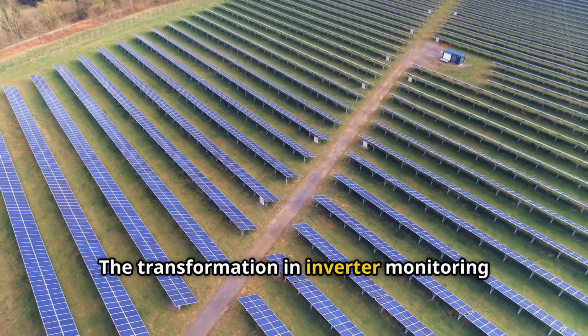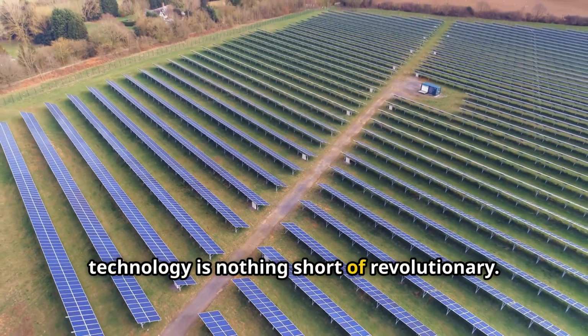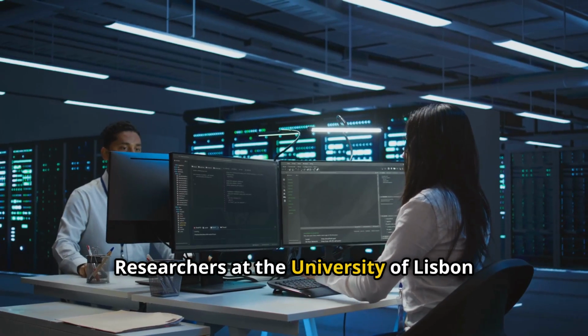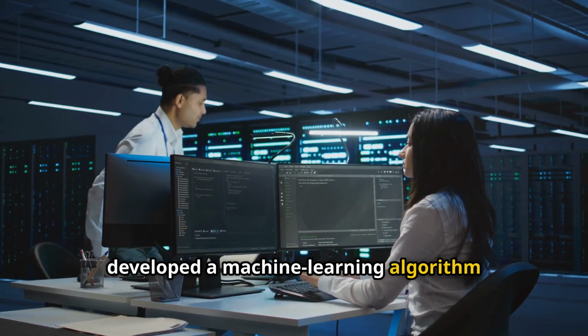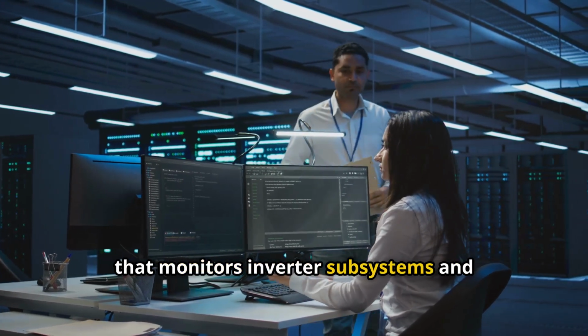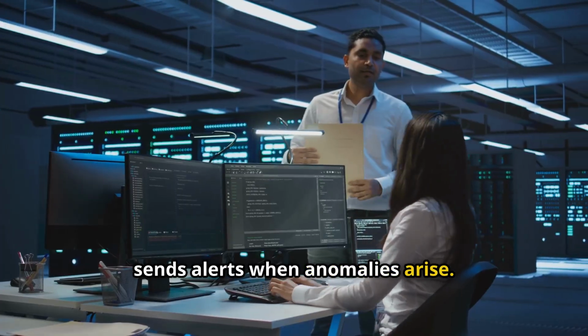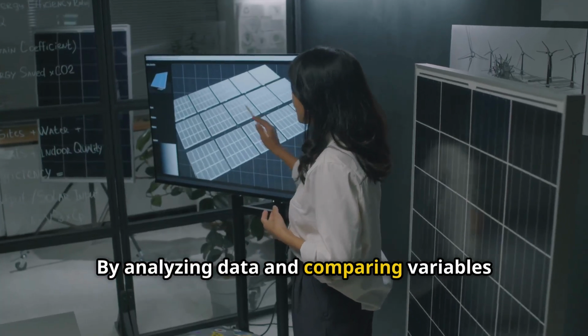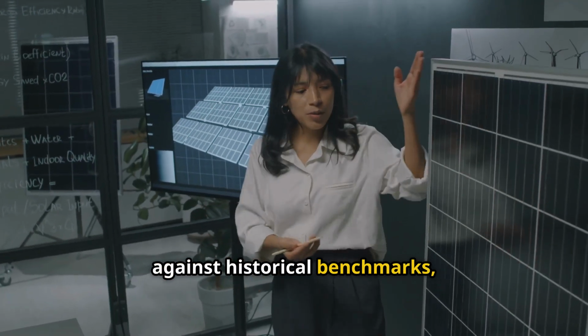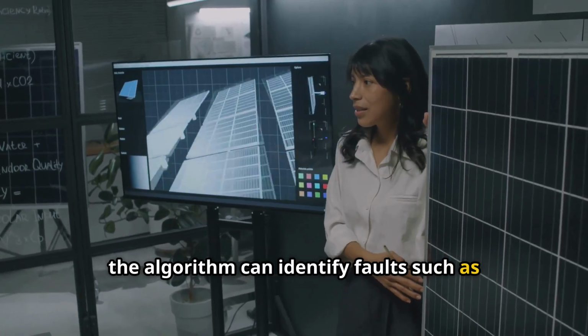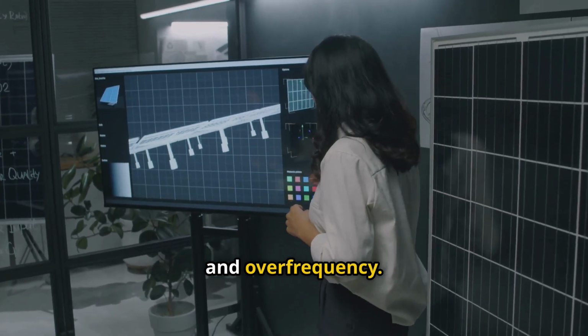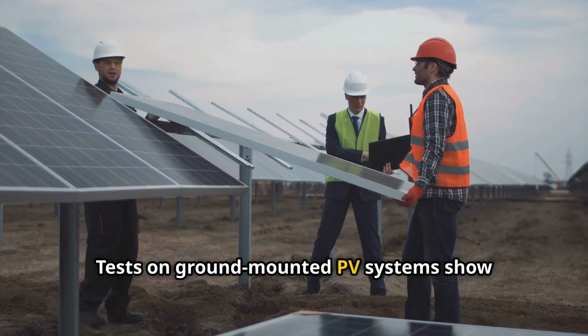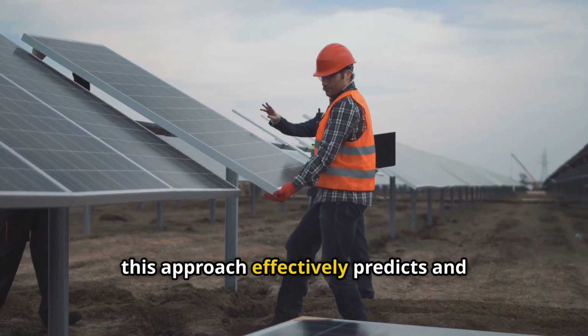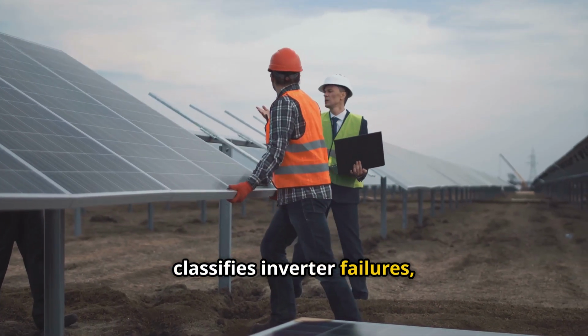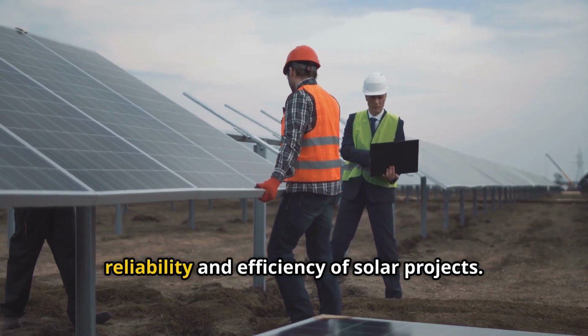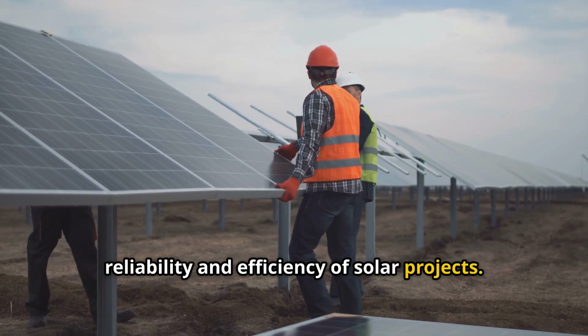The transformation in inverter monitoring technology is nothing short of revolutionary. Researchers at the University of Lisbon developed a machine learning algorithm that monitors inverter subsystems and sends alerts when anomalies arise. By analyzing data and comparing variables against historical benchmarks, the algorithm can identify faults such as grid overvoltage, undervoltage, and overfrequency. Tests on ground-mounted PV systems show this approach effectively predicts and classifies inverter failures, highlighting its potential to boost the reliability and efficiency of solar projects.